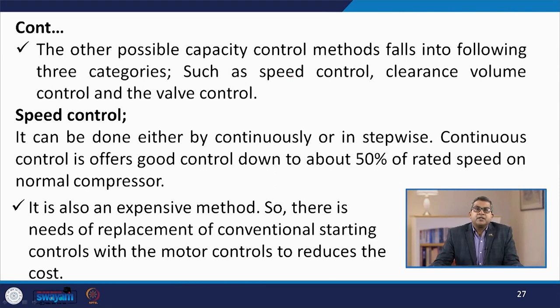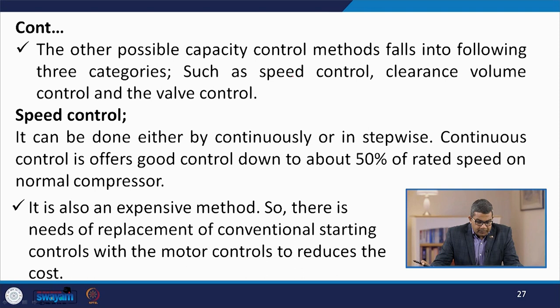Speed control can be done either continuously or in a stepwise manner. Continuous control offers good control down to about 50% of rated speed on normal compressors, but it is also an expensive method, requiring replacement of conventional starting control with motor control to reduce cost.